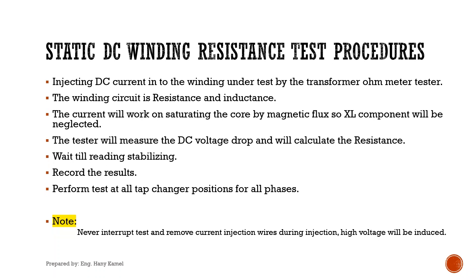Now we will discuss static DC winding resistance test procedures. DC current is injected into the winding under test by the transformer ohmmeter tester. As we know, the winding circuit is resistance and inductance. The DC current will work on saturating the core by magnetic flux, so the XL component will be neglected. The tester will measure the DC voltage drop and calculate the resistance. Wait until the reading stabilizes and record the results.